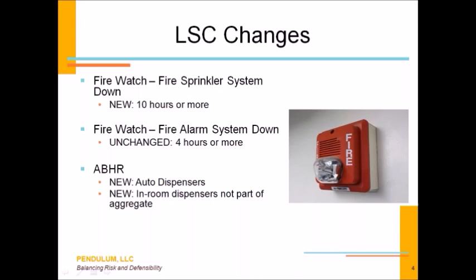So make sure that in practice, whenever any fire suppression or fire alarm system is compromised, your team goes on high alert and you're going into a fire watch. But when it comes to the codes and regulations, you have to go into a fire watch when your fire alarm system is down for 4 hours or more in a 24-hour period, continuous, or your suppression system goes down for 10 hours or more.